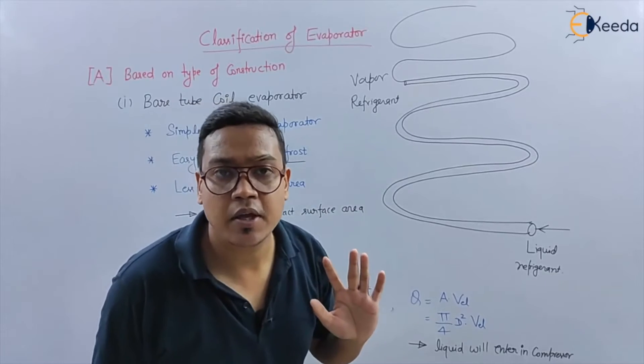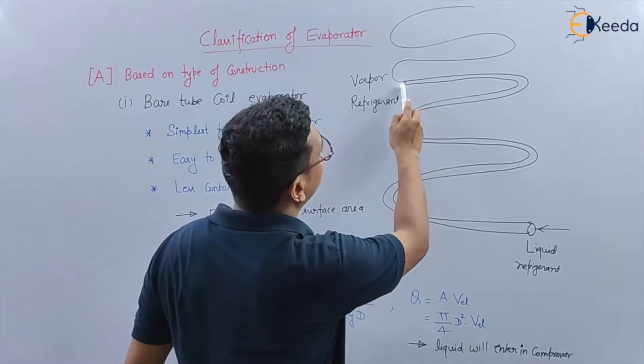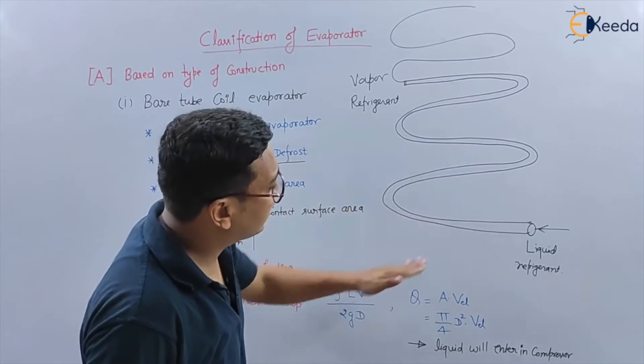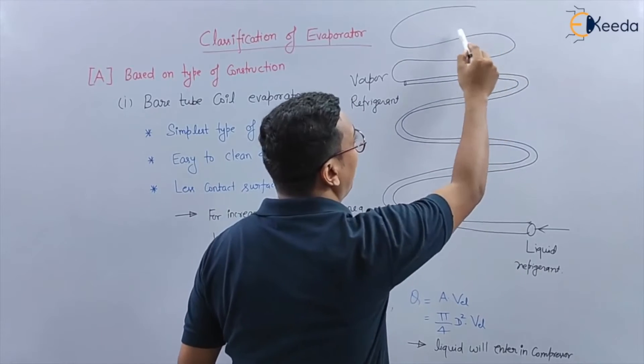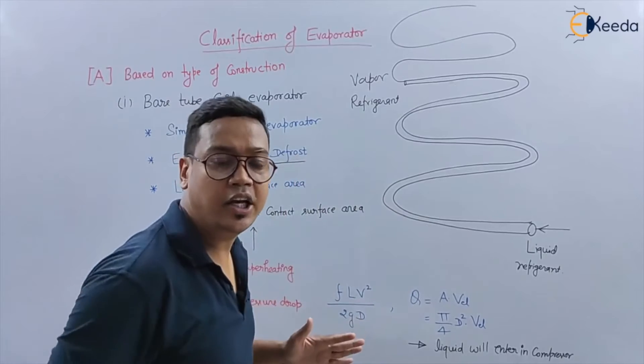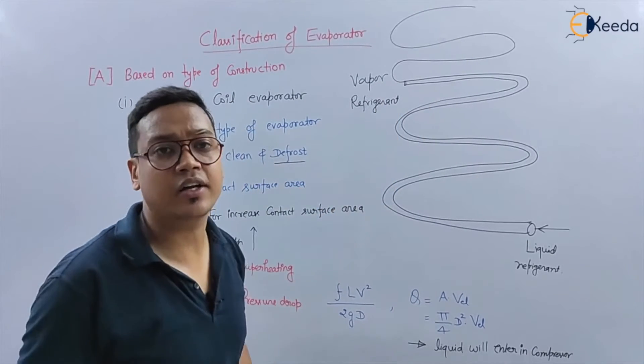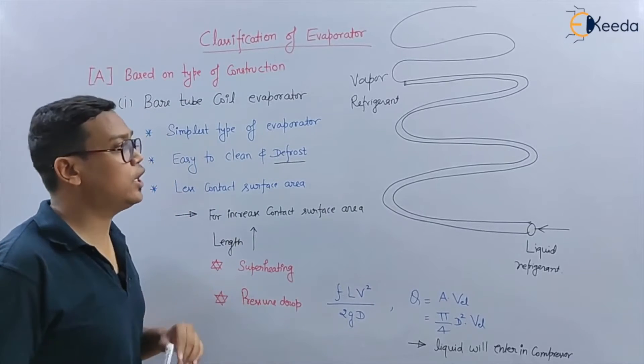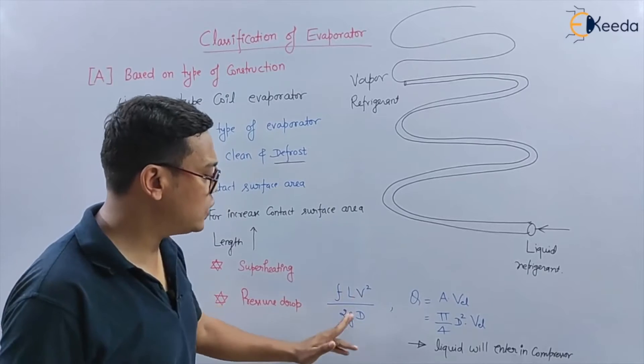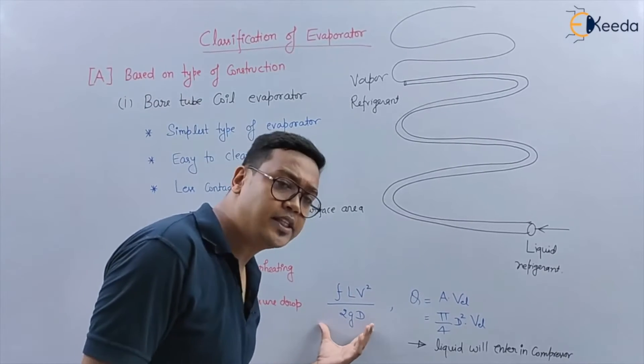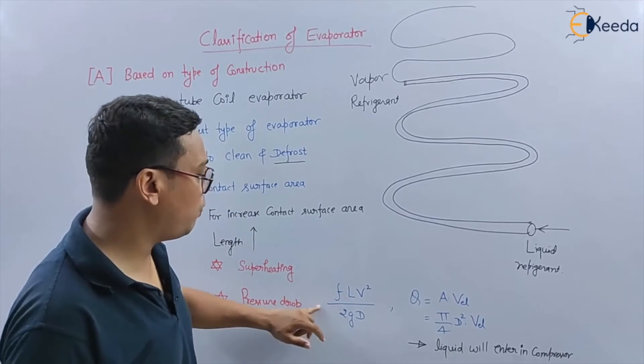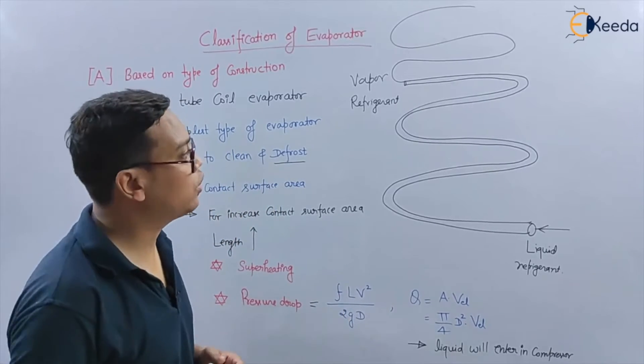Superheating will take place because by increasing the length, the refrigerant takes heat from the extra tubes as well, resulting in additional heat absorption. Also, pressure drop will increase with length, as given by the equation: ΔP = fLV²/2gD. If you increase the length, the pressure drop will increase.